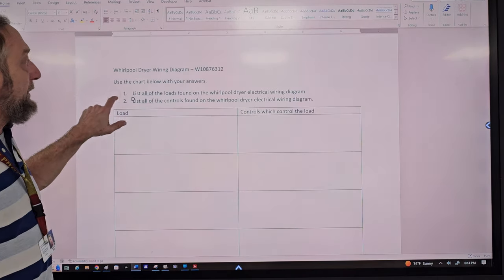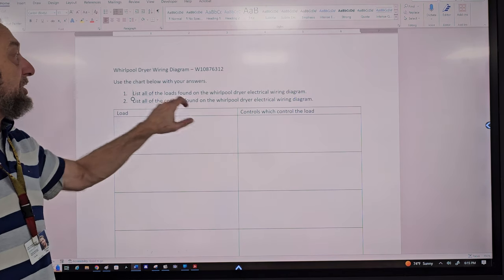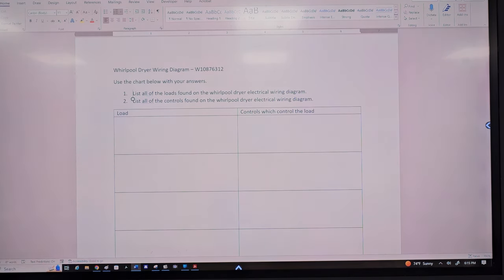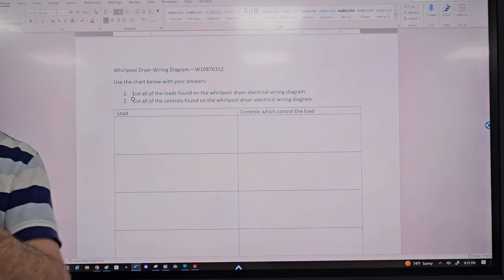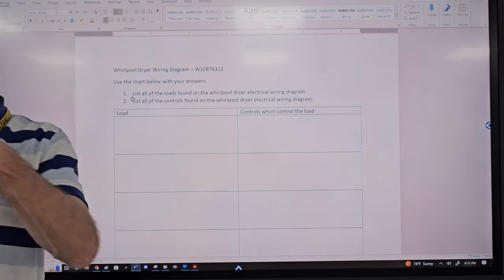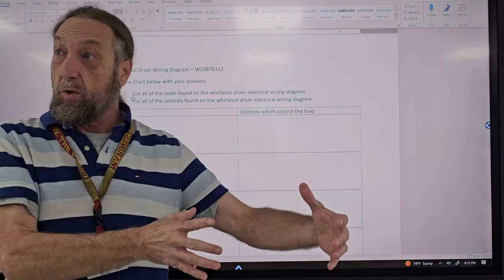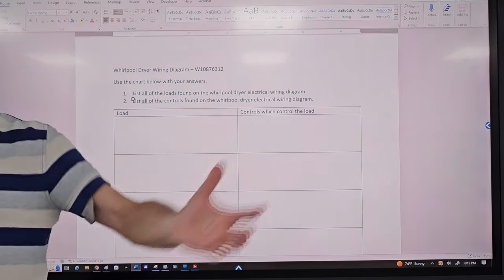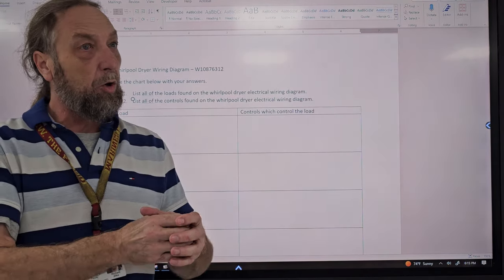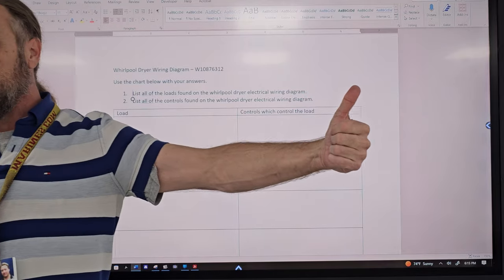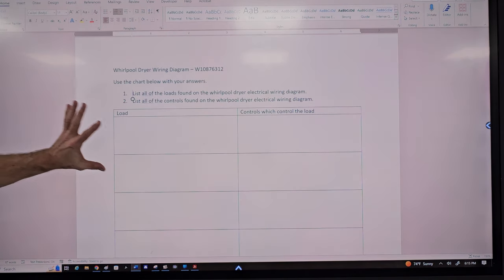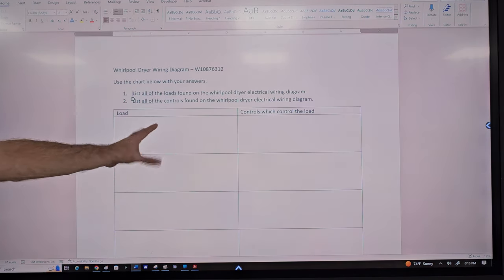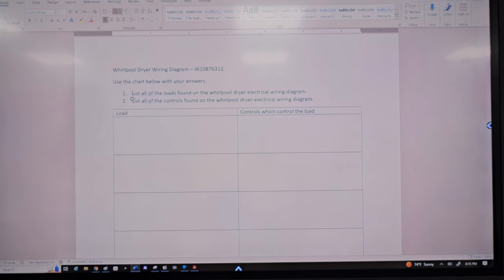What I wanted was to list all the loads and then list the controls that control those loads. Some people were confused about whether something is a load or a control. Some parts have both built in, like a timer — it has a timer motor, which is a load advancing the timer, and timer switches, which are controls. The timer motor would be separate from the timer switches as far as loads and controls.